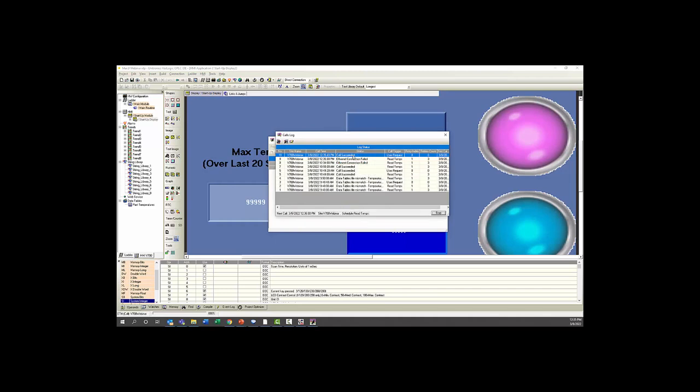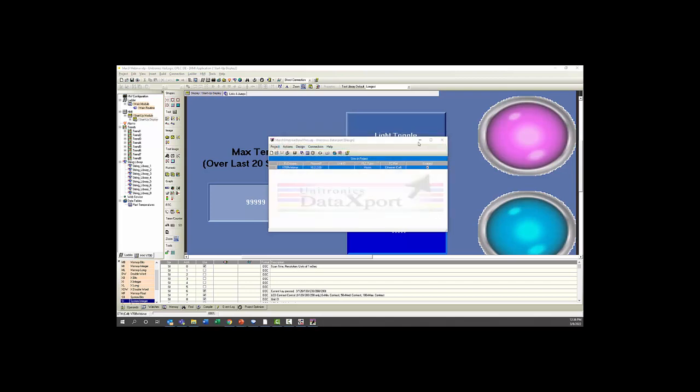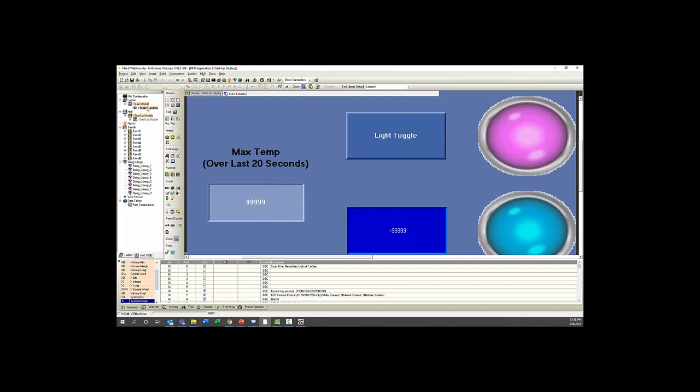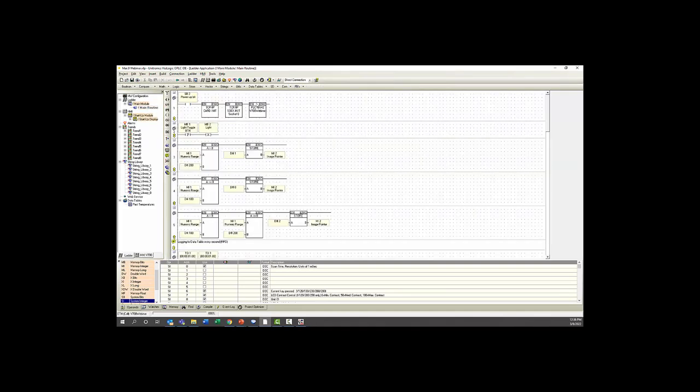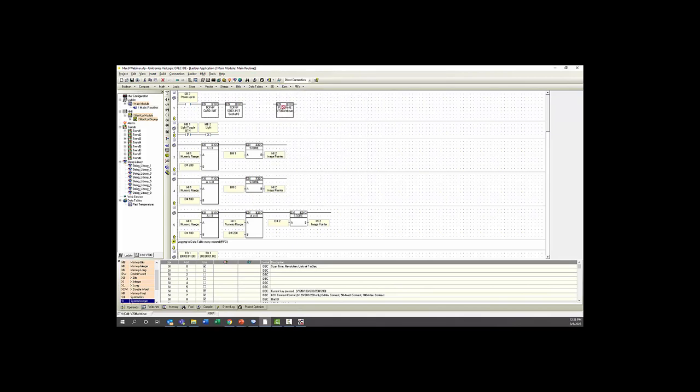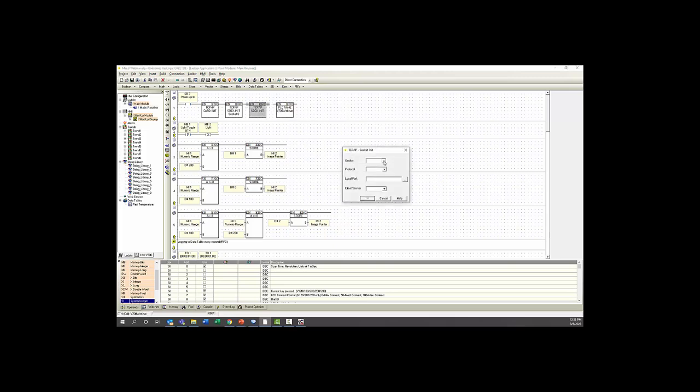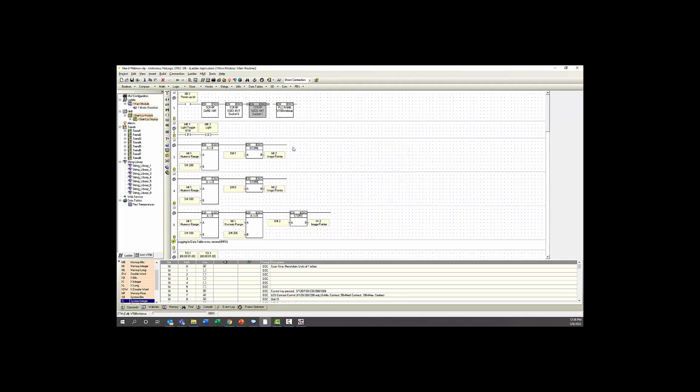So if you want to be able to run all of these things simultaneously, you would want to set up several different sockets so that you can use a different connection port for each method of data collection or PLC communication that you want to use. So if we wanted to do that in Visilogic, it would be as easy as going to com and doing another TCP IP socket init. And this time we're going to use socket one on TCP with a local port of 20257, so it's different from the first one. And it is also going to be server. And because we have connection, we can also remotely download to our PLC.